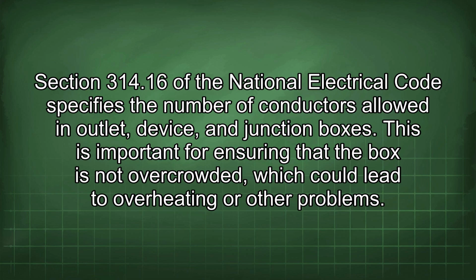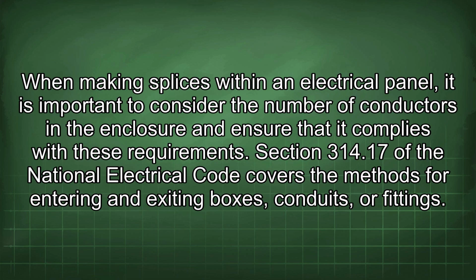Section 314.16 of the National Electrical Code specifies the number of conductors allowed in outlet, device, and junction boxes. This is important for ensuring that the box is not overcrowded, which could lead to overheating or other problems. When making splices within an electrical panel, it is important to consider the number of conductors in the enclosure and ensure that it complies with these requirements.